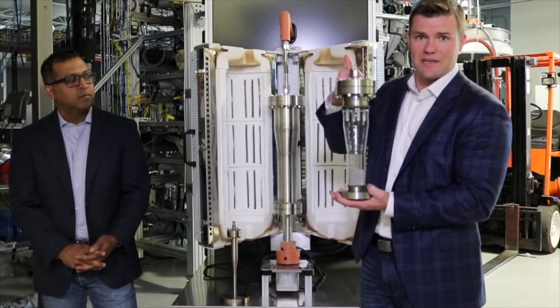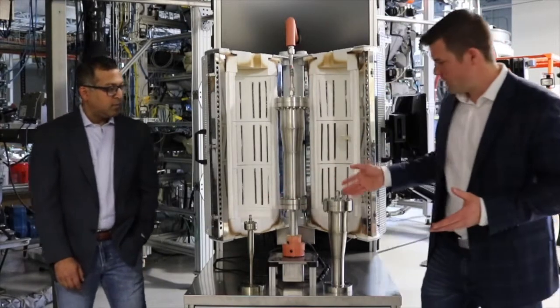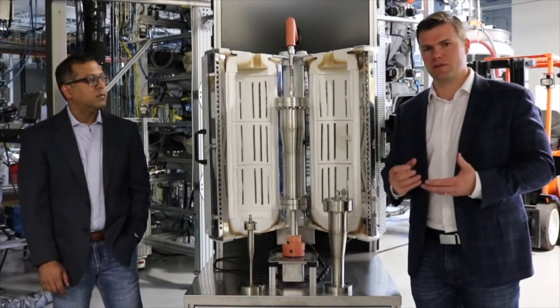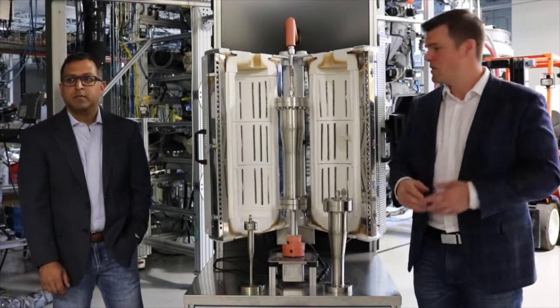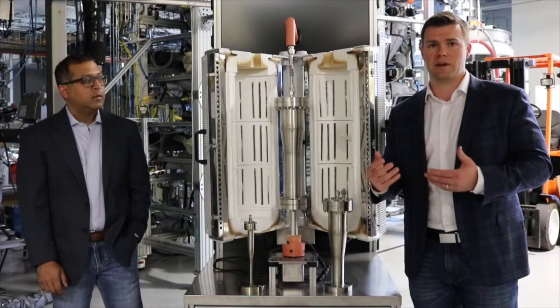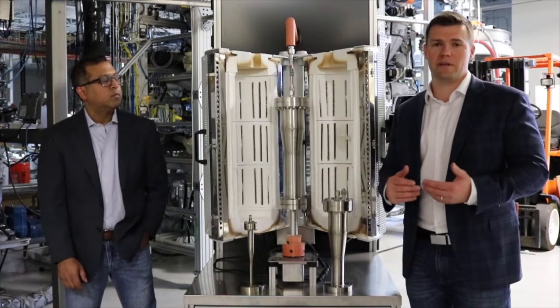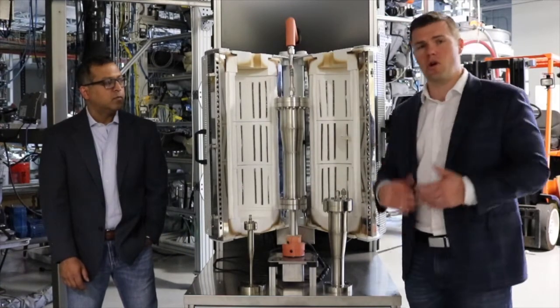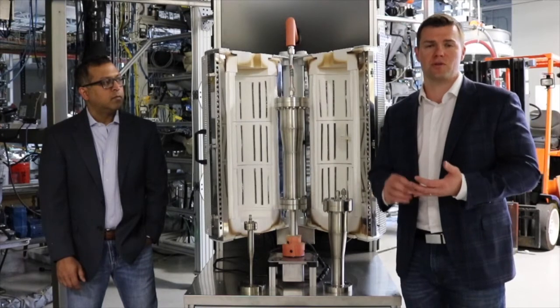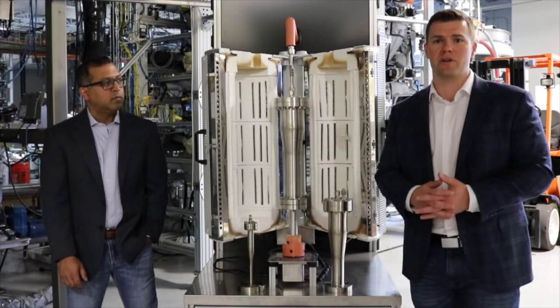Which just separate out the gas products. Here you can see the full range of capabilities within the Prometheus system from small, medium, and large scale reactors. These systems allow you to test different materials that you may only have small quantities of, but also scale those up to a level that's going to be prototype or early commercialization scale. Our small and medium sized reactors are capable of being loaded and unloaded in a glove box and put onto the system all under inert conditions. That way, for a material that has reactivity with moisture or oxygen, you can still put that on the system and coat it without exposing it to some unknown conditions.